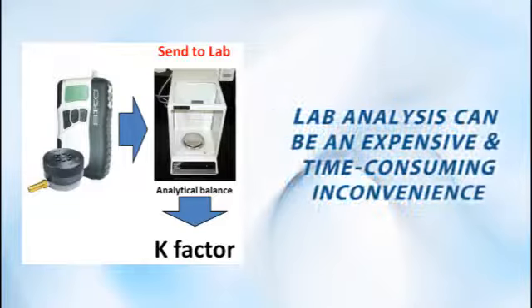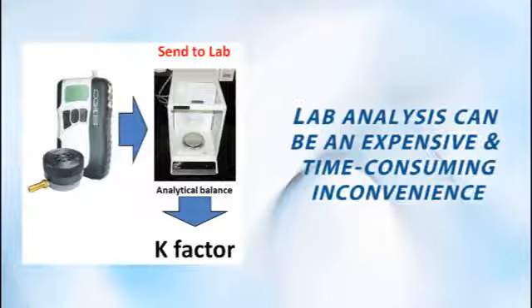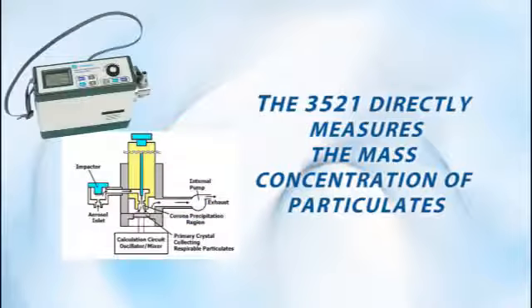In order to obtain the correct k-factor, a sample must be sent to a laboratory and analyzed. This process needs to be repeated each time new material is sampled. The 3521 doesn't require a k-factor since it directly measures mass.